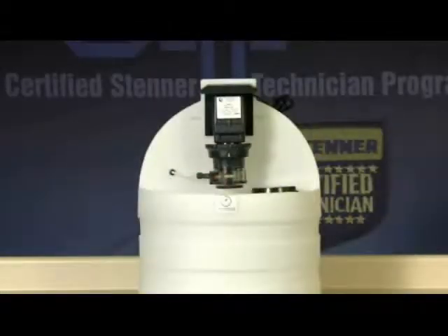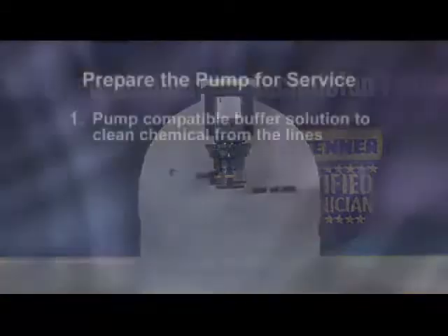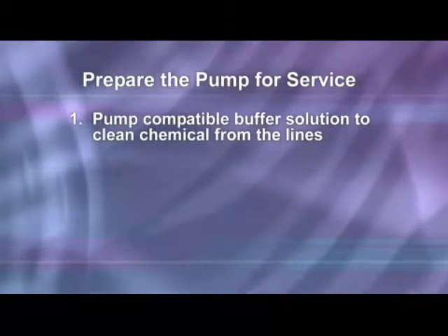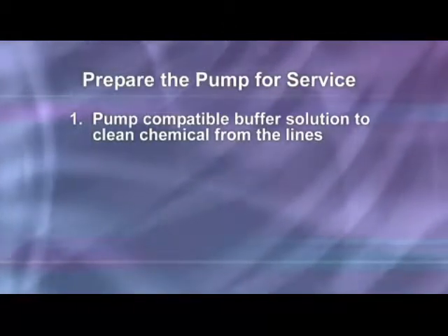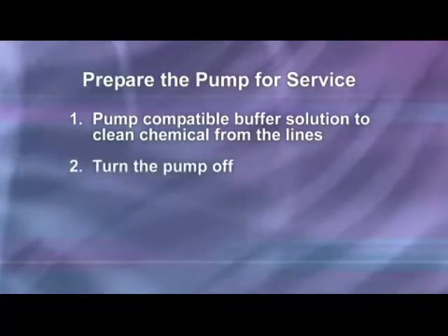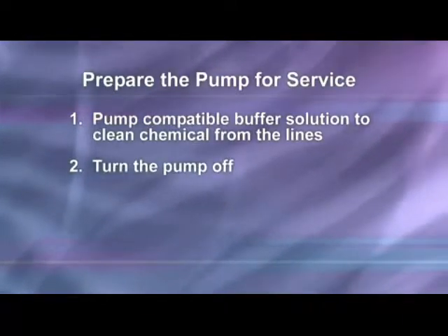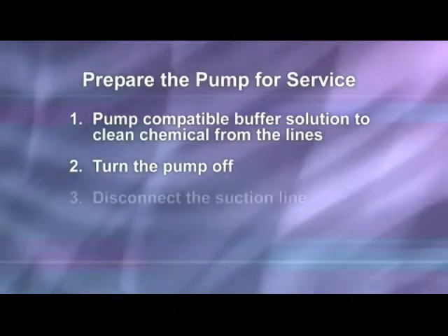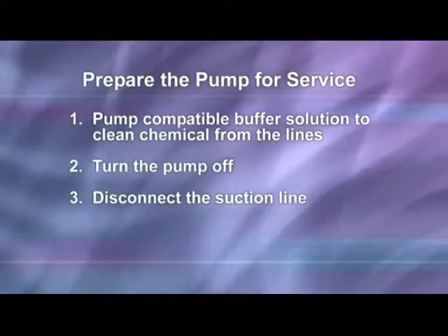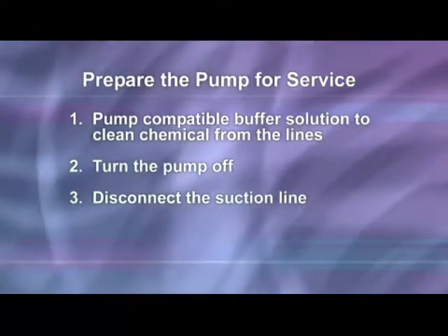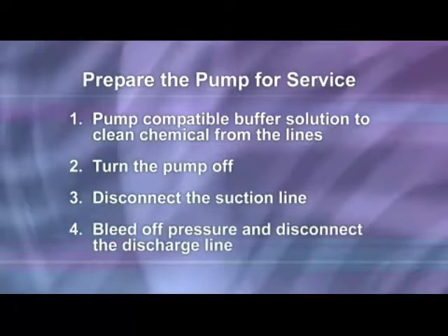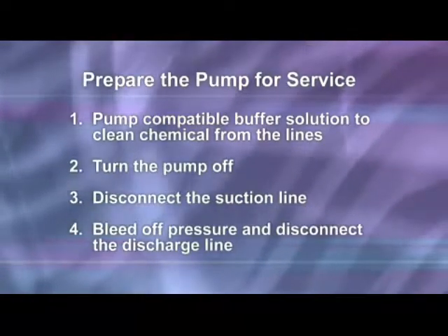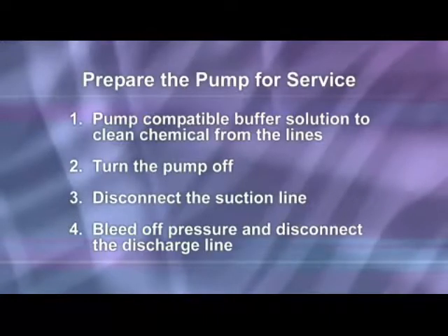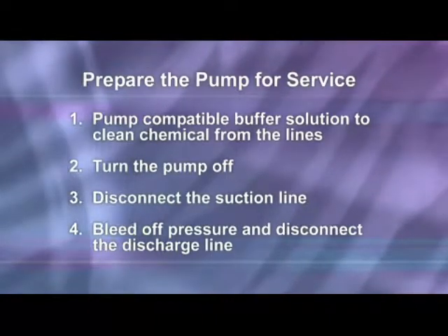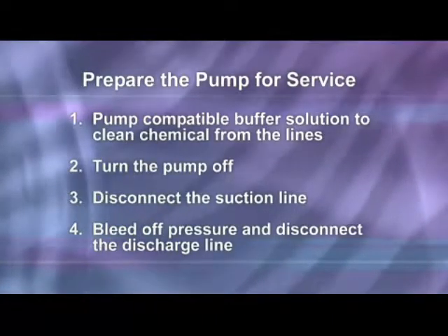Preparing the metering pump for service can vary by application, but in general will consist of the following steps. Pump a compatible buffer solution through the pump for several minutes to clean the chemical from the lines. Turn the motor on-off switch to the off position, which is down or to the rear of the pump. Disconnect the suction line from the pump tube suction fitting labeled in on the pump head cover. Before disconnecting the discharge side, bleed off any pressure. Then, disconnect the discharge line from the pump tube discharge fitting, labeled out on the pump head cover.